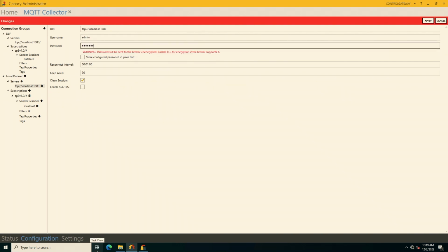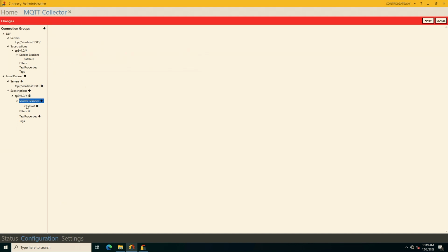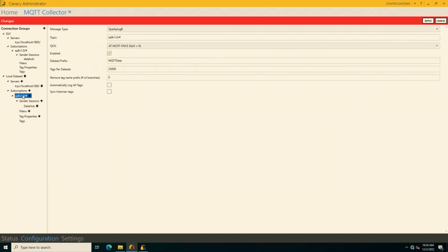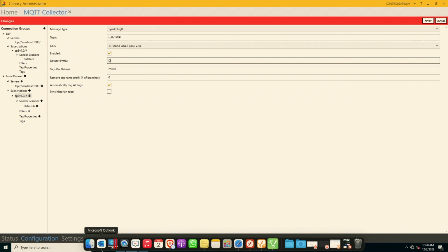You can have as many data collectors as you want pushing to your data set. You can even have those collectors pushing to multiple data sets. So you can create a nice high availability network that way. So what Tebe is doing now, he is just pointing the MQTT collector to the same MQTT broker that Laura is pushing the edge data to. And each one of those Canary collectors also natively have local store forward capability for added redundancy.